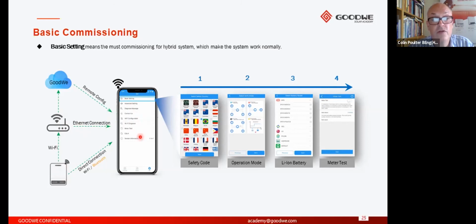However, whatever method you choose, we do have a sequence of steps that you need to go through in order to be able to set up the system correctly. The first thing you'd need to do is set the country code. So obviously here in the UK, we have G98, G99, so you choose the appropriate country code. You then step on to the next part of the sequence, which is setting the operation mode. As I said earlier, by default, you'll enter this mode here at the top left, general mode. Then you press next, which takes you on to the screen for configuration of the batteries.